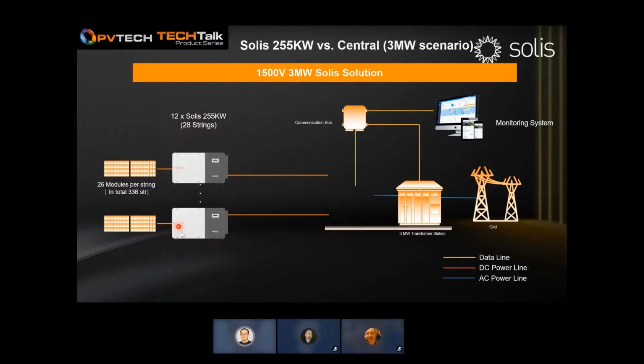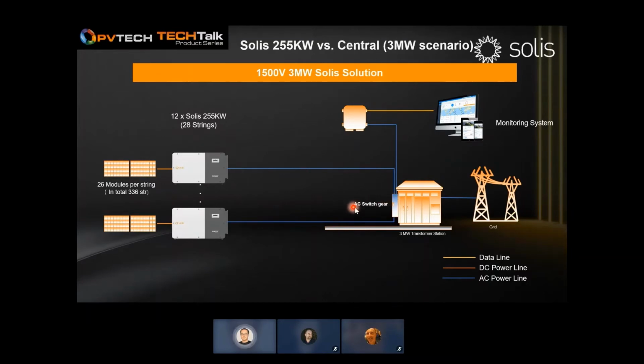So after we have installed the string inverter at these locations, the cable coming out is no longer DC. So we will change it to AC power line. And then we will need a merging device. We will add an AC switchgear to combine all this AC wire in. If you realize there's an AC wire coming out and going into a smart communication box, and that is not an error. We have implemented so-called PLC, the powerline communication technology, to allow data to transmit through the power line.